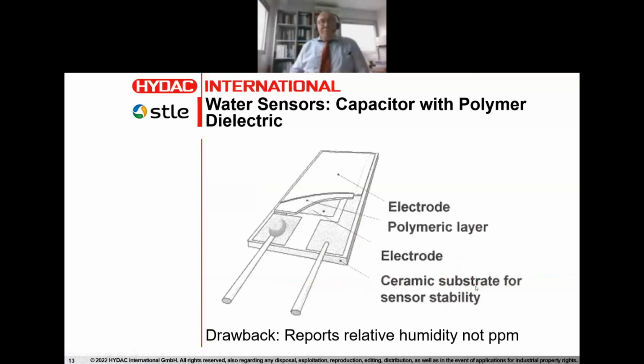So switching over now to the water sensor, the difficulty here is the transfer of information, or the correspondence of information, between what we measure online and what we measure in the lab is not one-to-one. And it's simply simpler to measure relative humidity in a normal system, but unfortunately that does not tell us what is the actual content, water content in ppm. And since a lot of these specs are based on engineering requirements and engineering specs, people are used to the tables, and they are used to seeing certain numbers written into the table, and they would like to see one-to-one correspondence. And so it's not really instructive or beneficial to say the relative humidity is 40%, because it doesn't really mean anything to anybody.